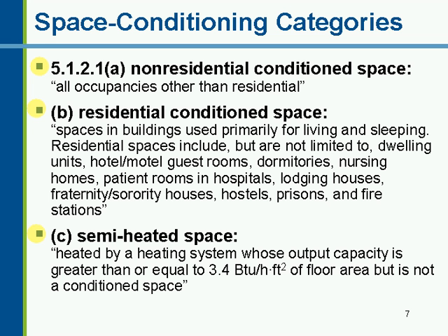Lastly, the other category is semi-heated space. And within that, it's a space heated by a heating system whose output capacity is greater than or equal to 3.4 BTUs per square foot, so 1 watt per square foot, but is not a conditioned space.